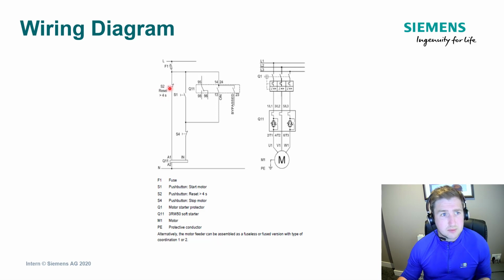And if that is pressed for a time which is greater than 4 seconds, the fault will be acknowledged, and then you can make a start again. So if you press start through S1, that will automatically trigger an initiation of the motor, providing that there's no faults or warnings. To stop the motor, all you have to do is press this S4 key here. At the moment, in this configuration, we're not connecting up 95, 96 or 98, which indicate whether there are any faults or any warnings. Here, we're only showing when the device has been switched on, but you can again show that the device has been bypassed also if you wish to. And that basically explains how you would connect up the soft starter.